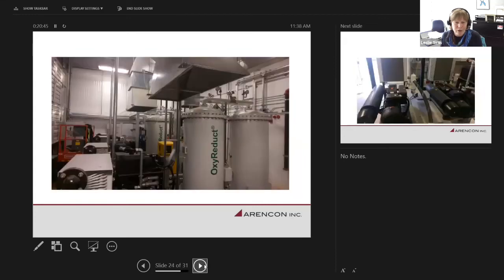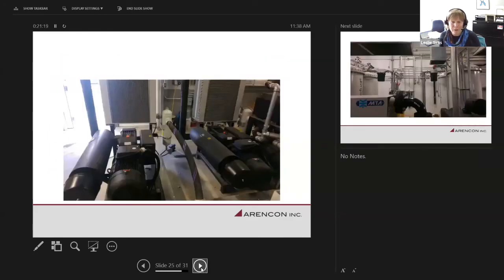Just another shot of the space. There was probably a comment about redundancy. There is emergency power provided to the controllers and to the sensors, so the brains and the intelligence and the monitoring are under emergency power. The physical plant, the mechanical components, don't require emergency power because we have the ability to shut the system down and we have a good hold time. A photo of the compressors.